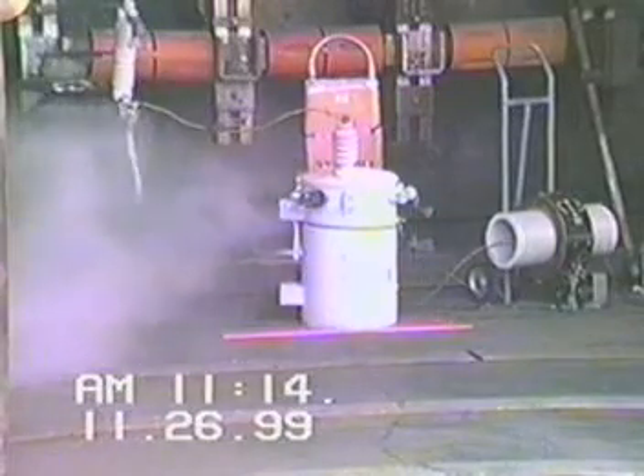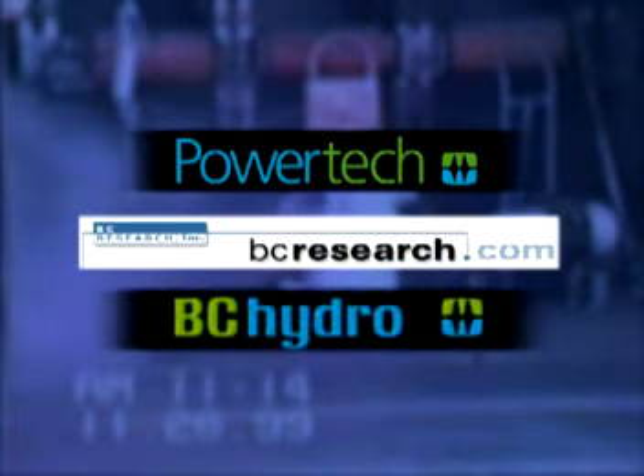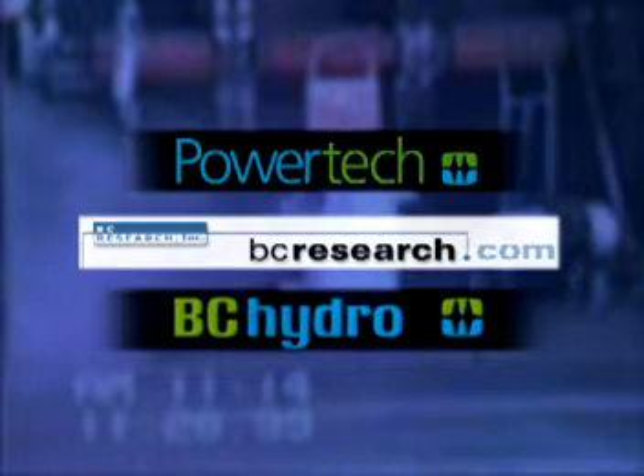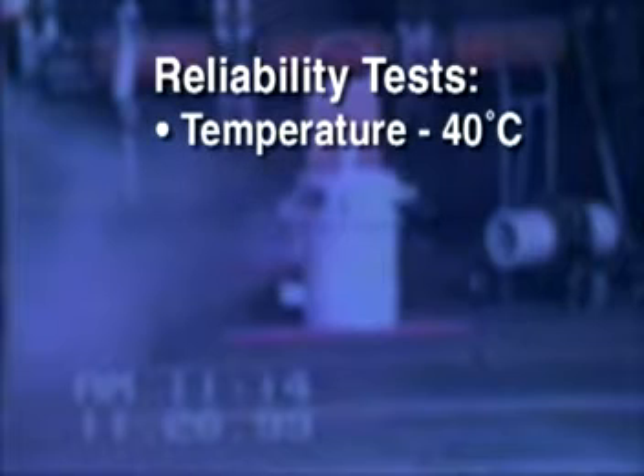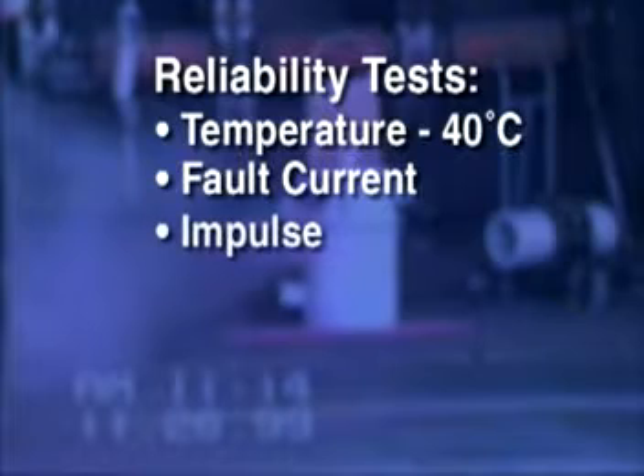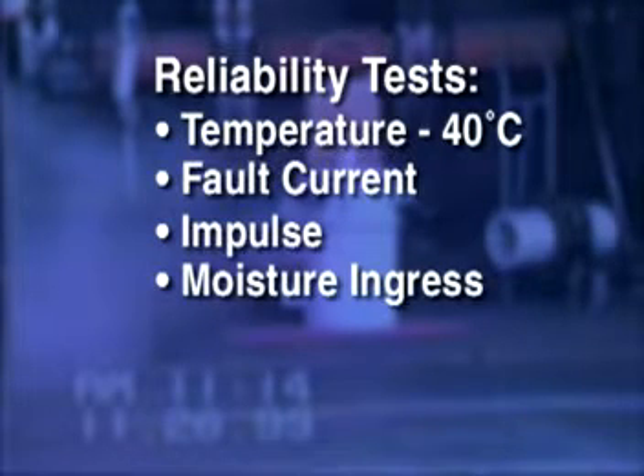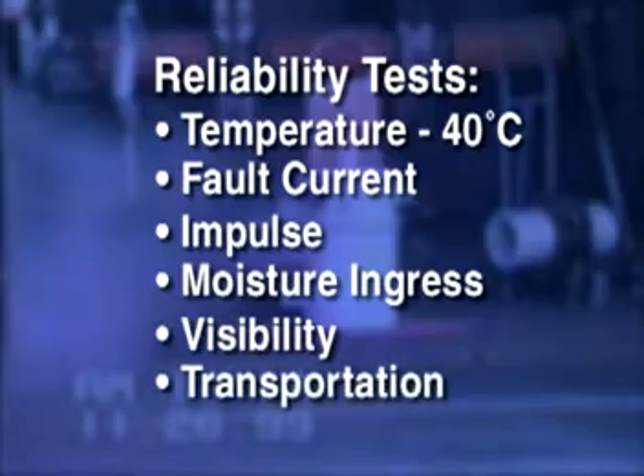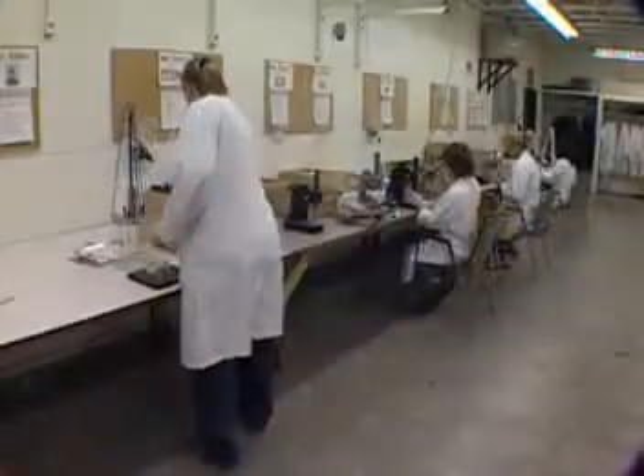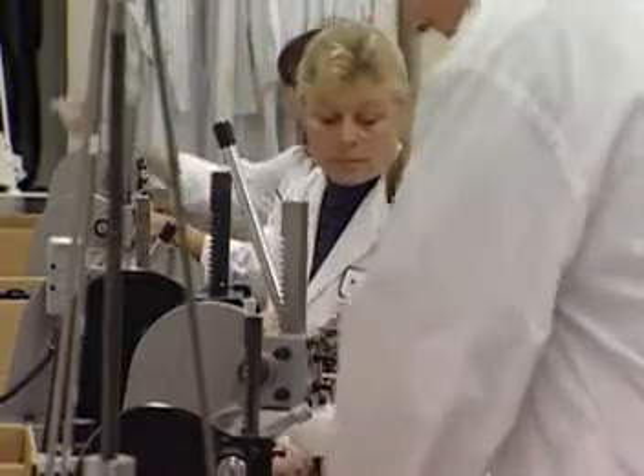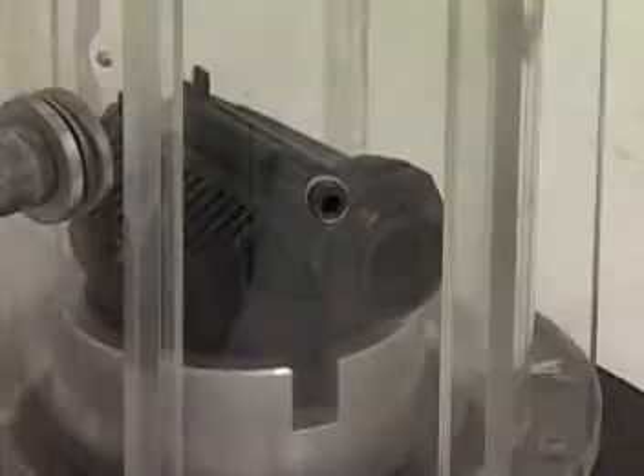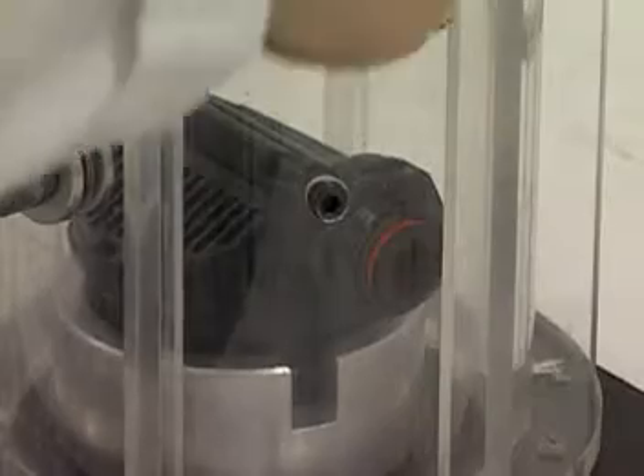The reliability of the IFD sensor has been confirmed through extensive laboratory conditions testing at PowerTech Labs, BC Research Council, and BC Hydro, as well as through system-wide in-service testing in small and very large utilities. Reliability tests were conducted for operation at temperatures down to -40°C, simulated fault current, impulse, moisture ingress, day and night visibility, and transportation. Strict inspections in the manufacturing process of the IFD assure consistent quality of the product and high-level performance to meet customer requirements.